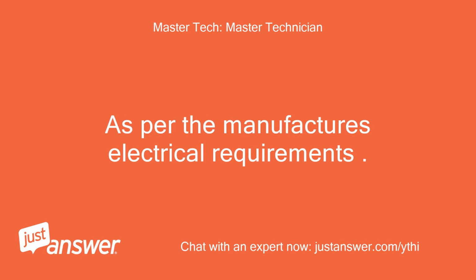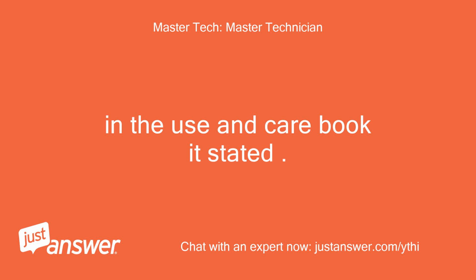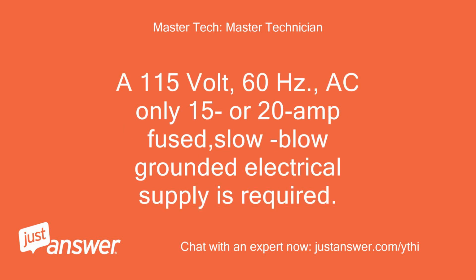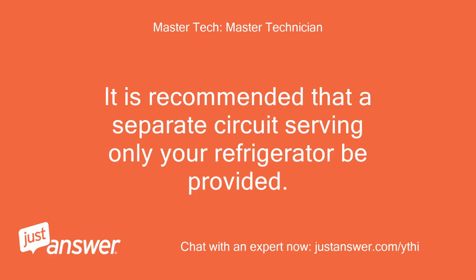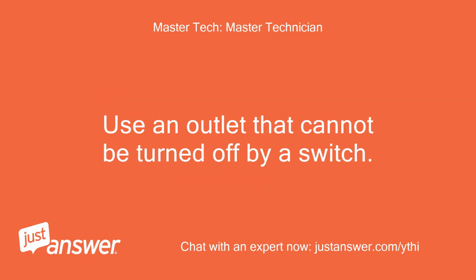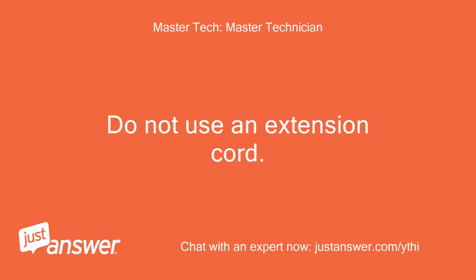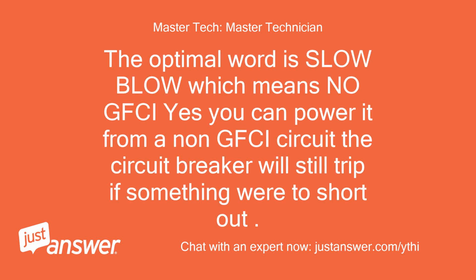As per the manufacturer's electrical requirements, in the use and care book it stated: a 115 volt, 60 Hz, AC only, 15 or 20 amp fused, slow blow, grounded electrical supply is required. It is recommended that a separate circuit serving only your refrigerator be provided. Use an outlet that cannot be turned off by a switch. Do not use an extension cord. The key word is slow blow, which means no GFCI.